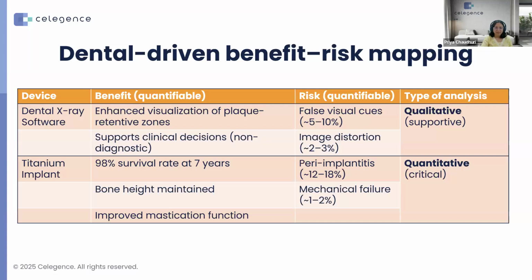So why are quantitative methods preferred for high-risk devices? Because they definitely provide objective proof. They provide predictable thresholds and traceable benefit-risk justification, especially based on the GSPRs that we have claimed. As I said, for class 1 devices with minimal risk, qualitative insights may still be sufficient, but even then they must be structured and benchmarked through the state of the art, and the strategy of the clinical data collection system must be well documented and defined in the CER, especially the CEP.